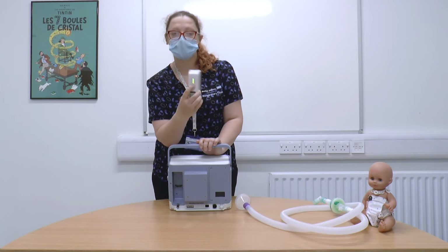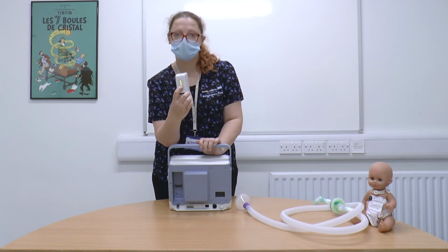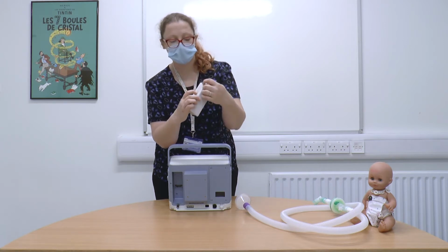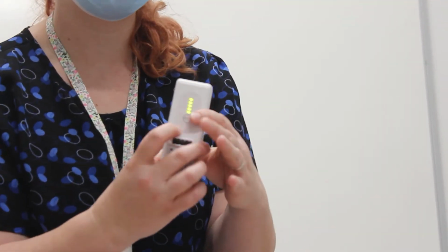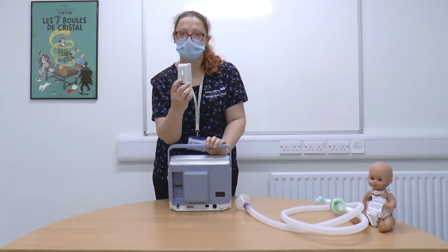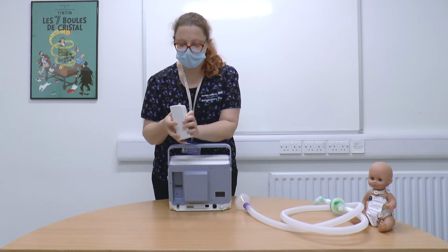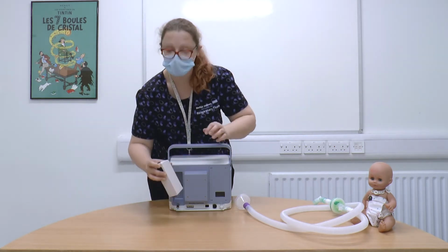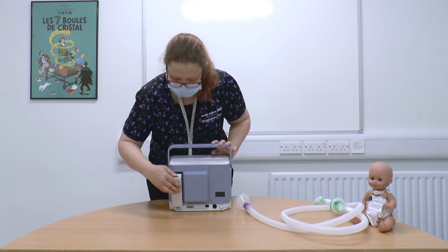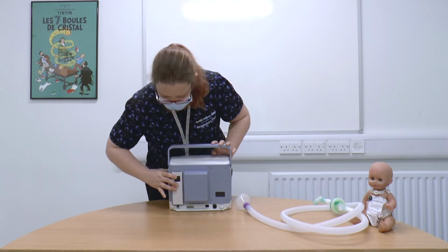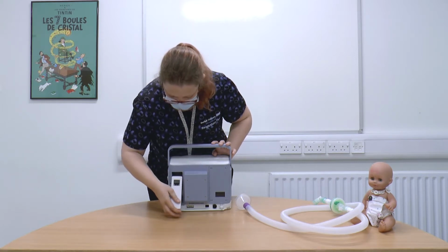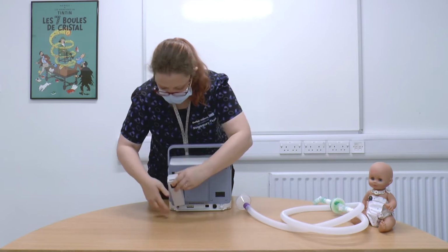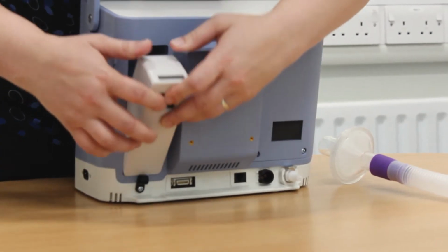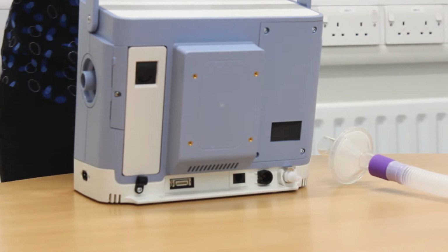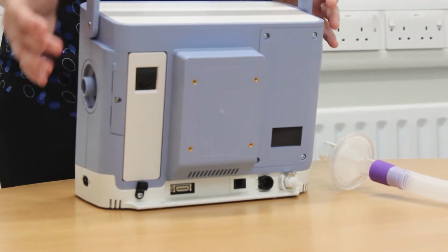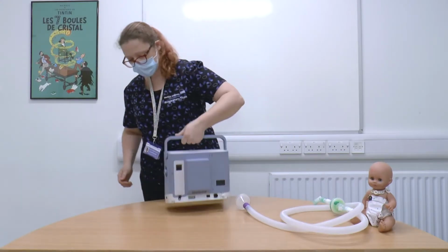If you rely on having at least 4 to 5 hours in this battery when fully charged, think of each glowing light as an hour of charge. So as there are 5 lines, you've got at least 5 hours. If a child is on lower flow, you may have more. To insert the battery, you simply place it in, bottom side down, and give it a push. It will click into place. If you gently shake it, it shouldn't move at all.